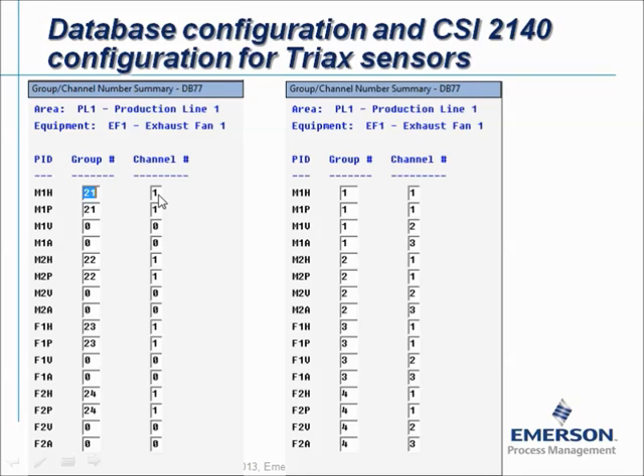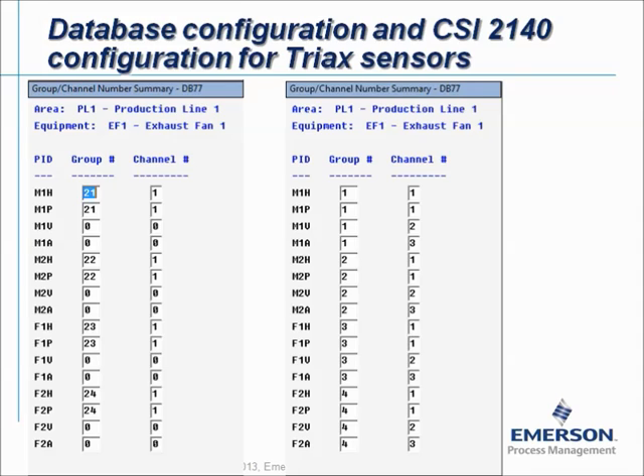If we want to work with a Triax sensor we have to change this configuration. All the measurement points that are in the same plane have to receive the same group number. For example, motor outboard gets group number 1, motor inboard group number 2, fan inboard group number 3, and fan outboard group number 4. If there are more than 4 bearing locations, simply continue with the next available number. When starting a new machine, you can restart with group number 1. Inside every group, channel 1 is horizontal, peak view is also channel 1, vertical is 2, and axial is 3.